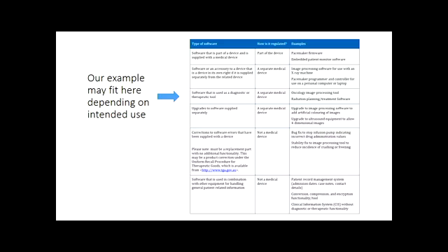When you said that software that requires hardware to achieve its purpose isn't regulated as a medical device, is the hardware itself regulated as a medical device? Yes. So the hardware itself would be. And that negates the need to regulate the software? Yes. So it would become a system, if that makes sense. And then if your attachment is going to be a class 2, your software is automatically going to be a class 2 and assessed as part of that device. Does that make sense? Because they'll look at the entire system, not just the small part that does the measuring. I hope that makes sense.